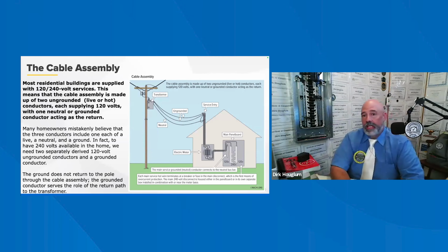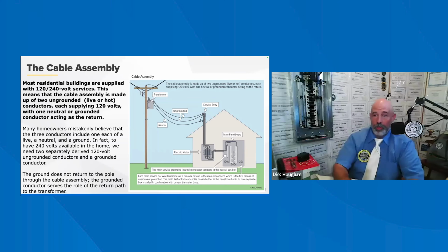That works. Each main service hot wire connects at the breaker or fuse in the main disconnect. This is the first overcurrent protection. The main 240 volt disconnect is housed either in the panel board or in its own separate box, usually installed near the meter base. The main service ground, the neutral conductor, connects to the neutral bus bar. Its location varies depending on what panel you have or the panel manufacturer. It is typically a silver color with many small holes and screws and one large hole for the main service ground wire.